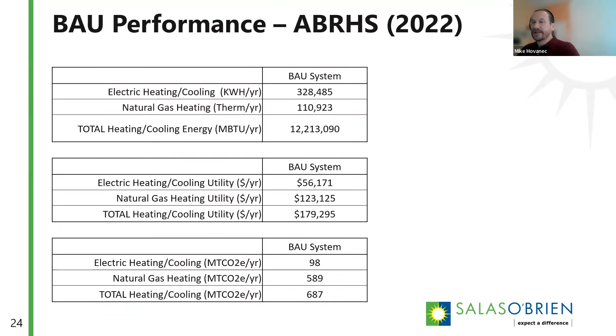For the high school's electrified system, we proposed a hybrid approach using multiple HVAC assets, since it's a very large building with many different end uses. First, a solar thermal array provides a small amount of annual heat to help cover the year-round heating load. Next, an optimized air source heat pump system provides the majority of the heating and cooling. Finally, to supplement the heat pump system and handle peak cooling and heating, we have an air-cooled chiller and an electric boiler.